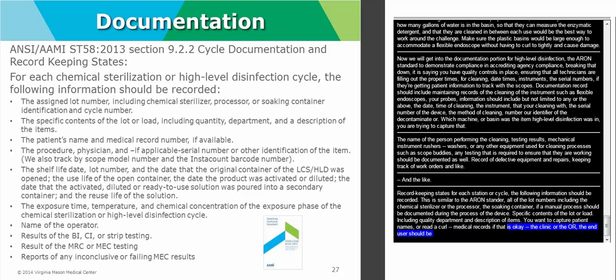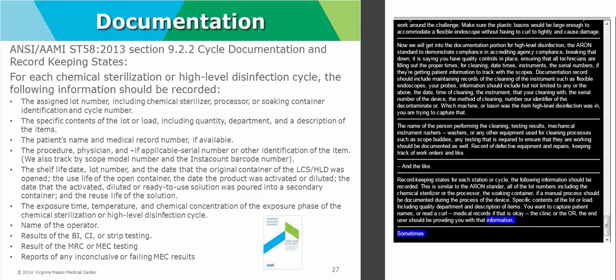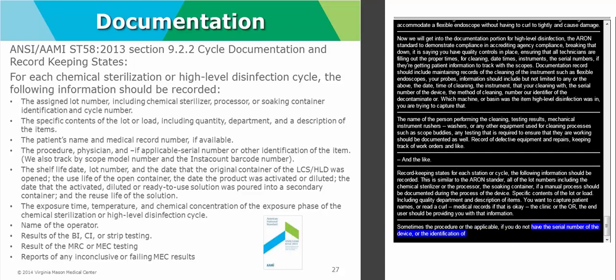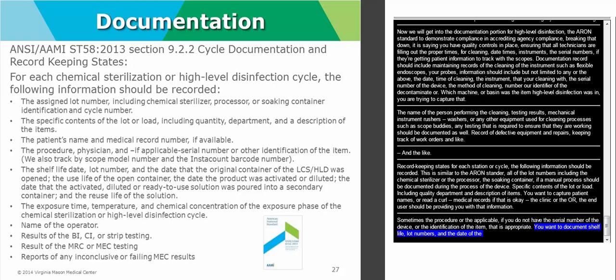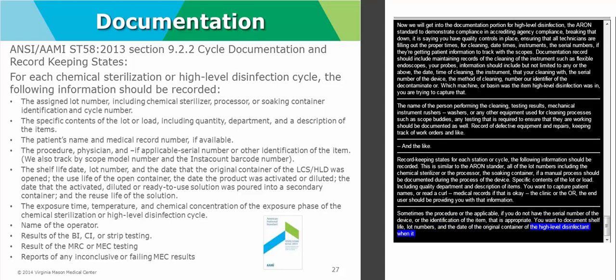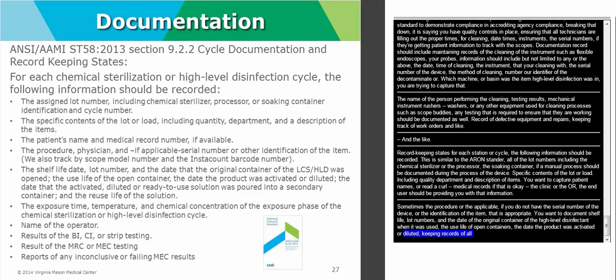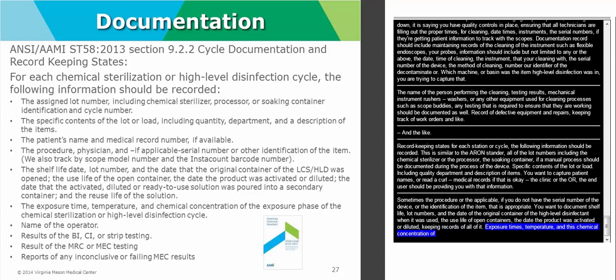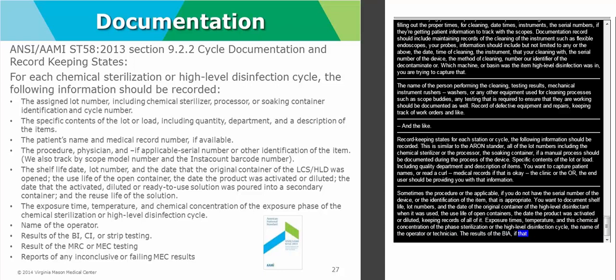Sometimes the procedure or physician, if it's applicable. If you do not have the physician name or procedure, the serial number of the device or the identification of the item is appropriate. You want to document shelf life, lot numbers, and the date of the original container of the high-level disinfectant when it was used, the use life of an open container, and the date the product was activated or diluted, keeping records of all of that. Exposure time, temperature, and the chemical concentration of the exposure phase of the chemical sterilization or high-level disinfectant cycle. Again, name of your operator or your technician. The results of your BI, which is your biological indicator, if that's required. Normally that's appropriate for your sterilization processes.